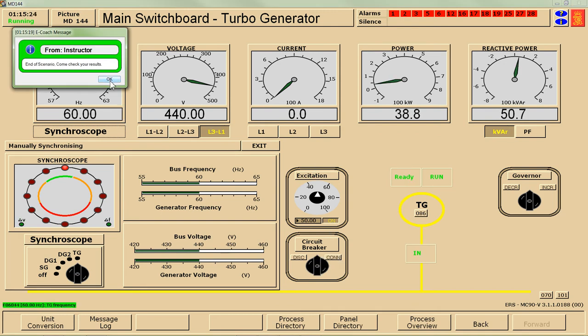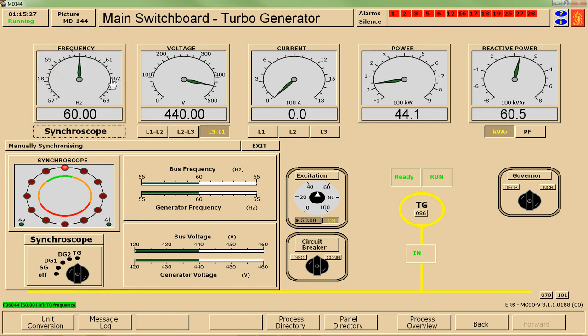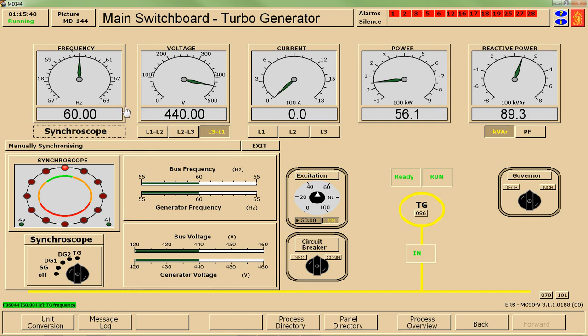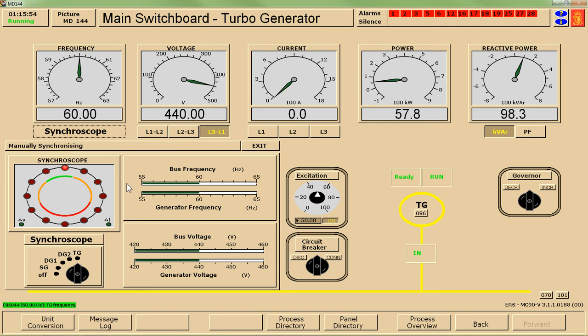Depending on your simulation, you may have a pop-up telling you that you have completed your simulation. Before we move on, I want to talk about a few things that have happened. Our frequency was slightly higher than 60 hertz, which is my bus frequency. Now that I've connected, it is locked in. You can see that my synchroscope is no longer free to move around — I've essentially locked in my generator. The electricity it's producing is now locked to the grid, so what is flowing through the wires it's connected to.